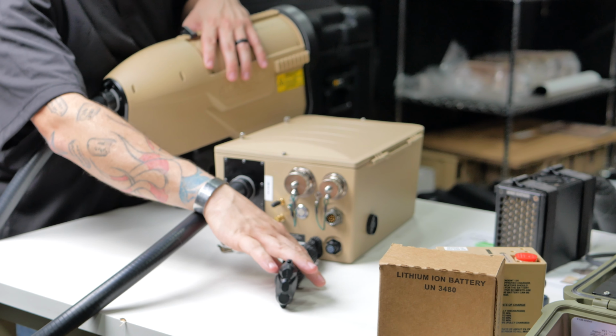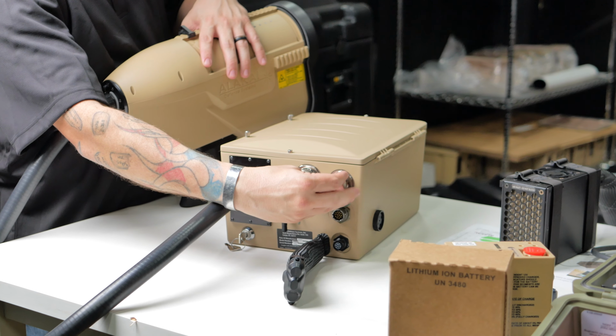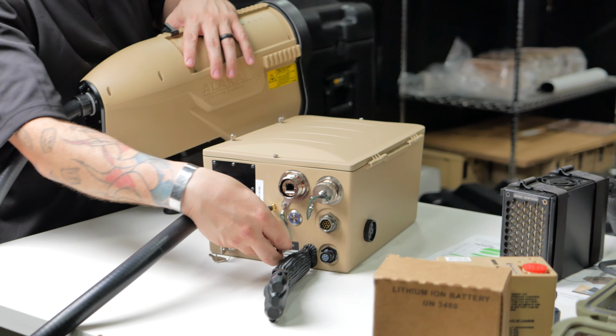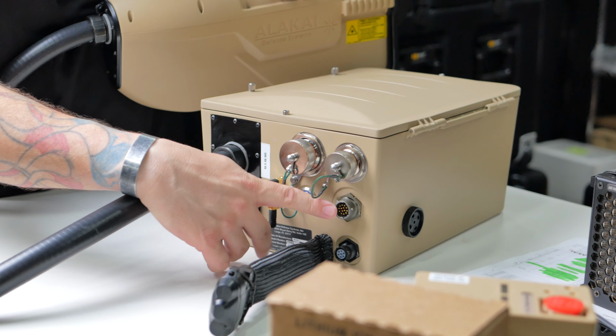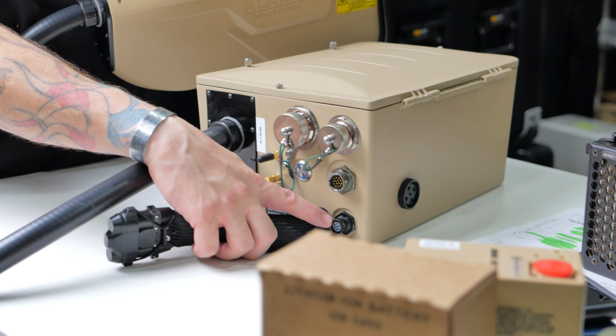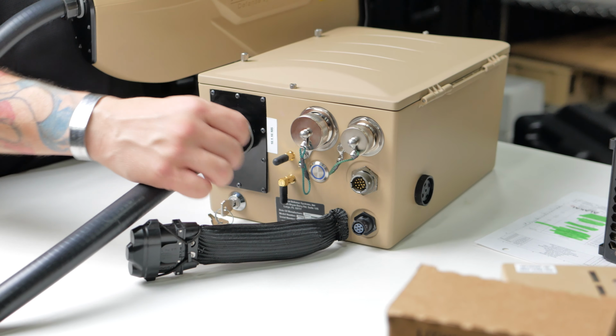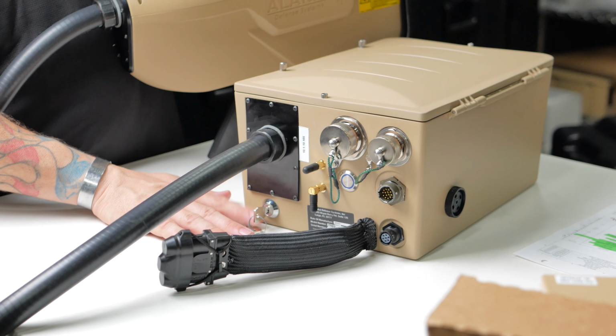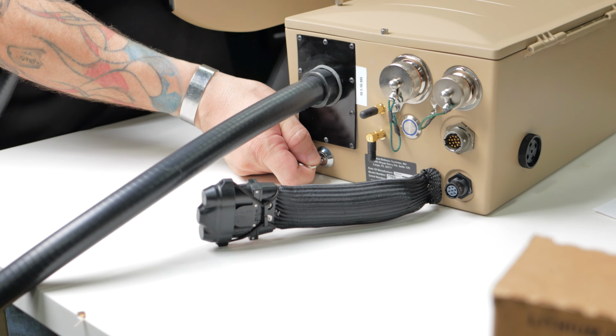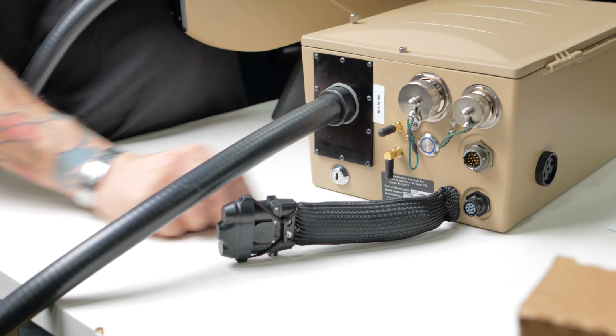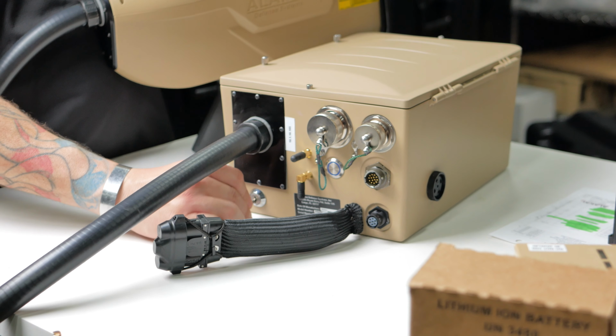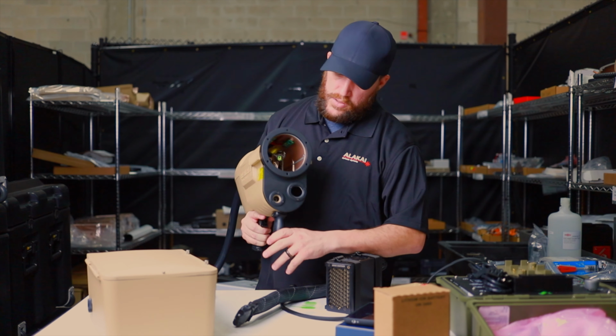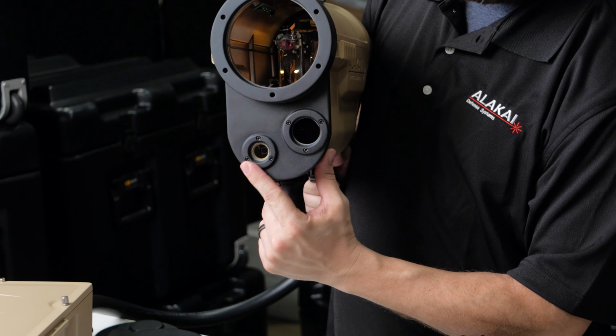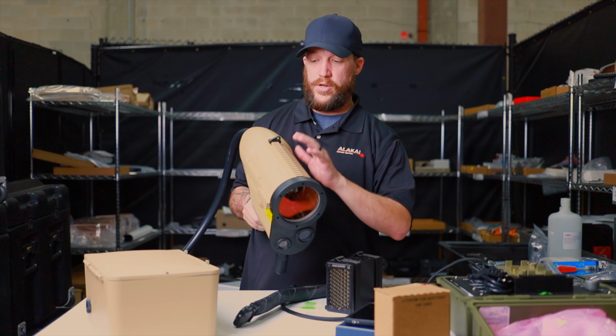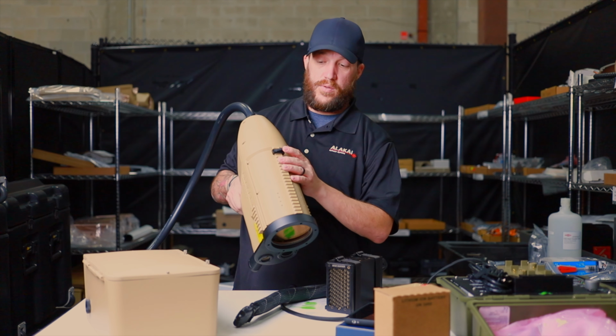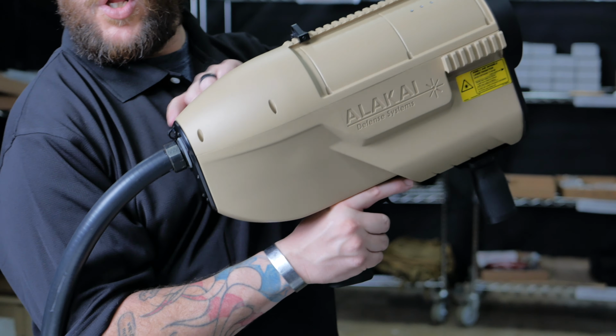So keep it laid on the table, on a breadboard, something that keeps your umbilical free of twists. We have our chiller water line, USB ports, Ethernet ports, main power supply, your chiller power supply, our power button, and then your 2 Wi-Fi and Bluetooth antennas. There's also an enable switch, which when it's in the locked position, you can remove it for safety, and you can't operate the system without this being engaged. We have our rangefinder window, our camera window, and our main output window. You'll also have your tactical sling tie-down point, one here and one on the back panel with a loop for you.